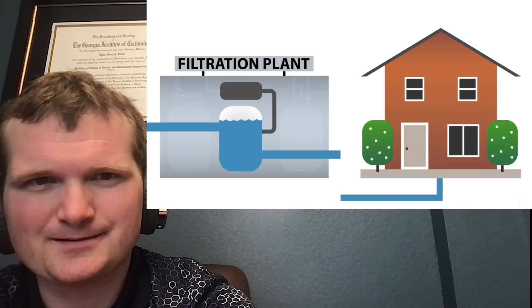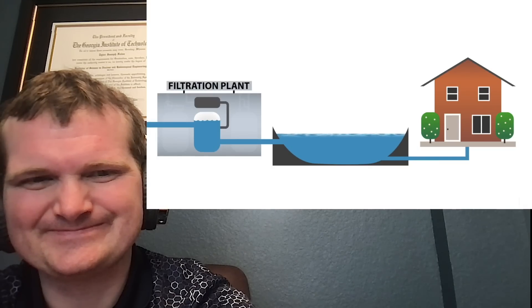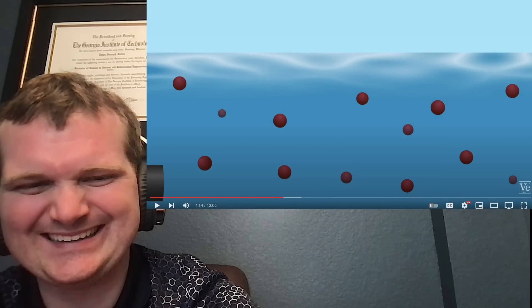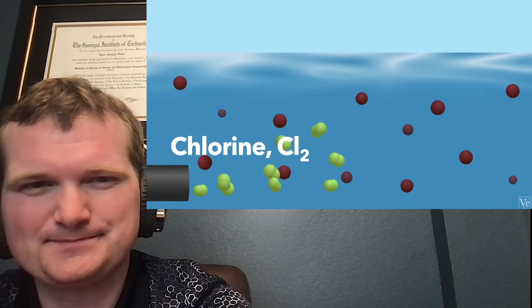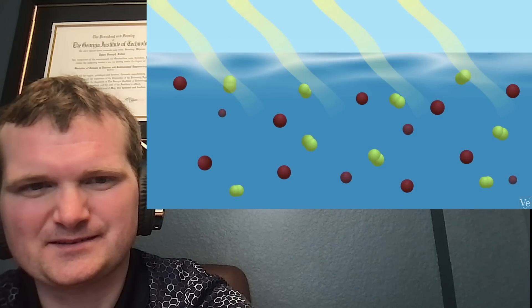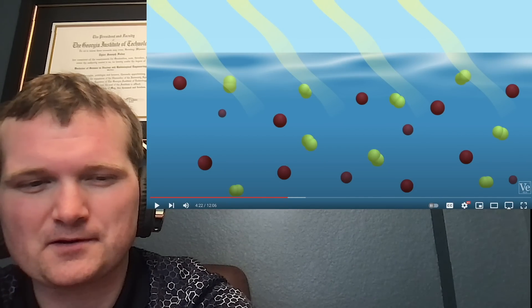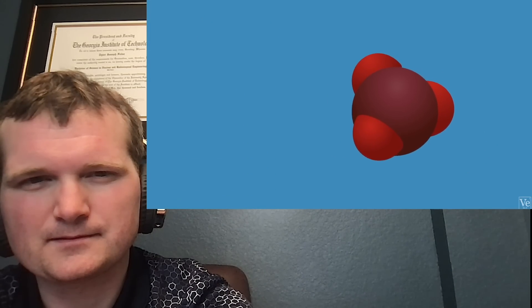Are you aware of this? We said, well, we don't show anything. But between the filtration plant and the customer was the reservoir. So they did some tests, and almost immediately upon the water coming into this open reservoir, the bromate levels jumped. It turned out that bromide with chlorine — which was supposed to be safe — in bright sunlight formed bromate even more than ozone. So I was on the right track, I just didn't mention bromate earlier. We made this unfortunate scientific discovery that actually was not part of any regulatory scheme, and so here we are at the reservoir.